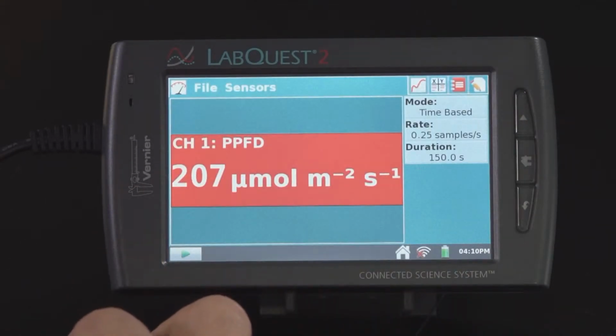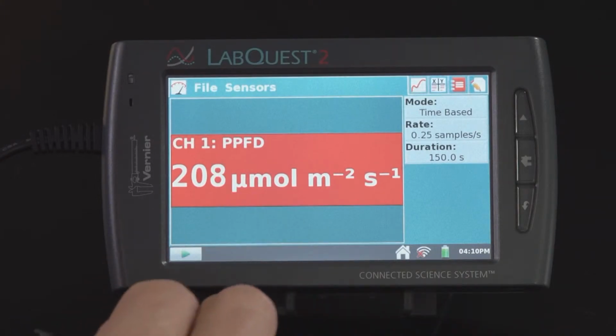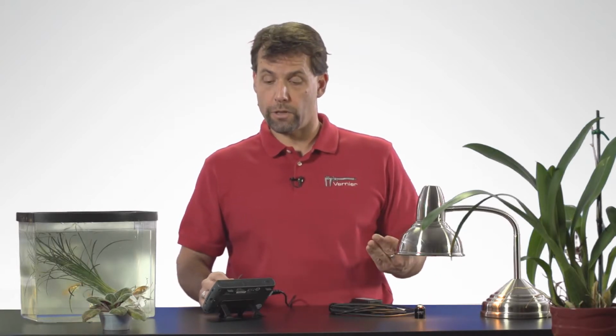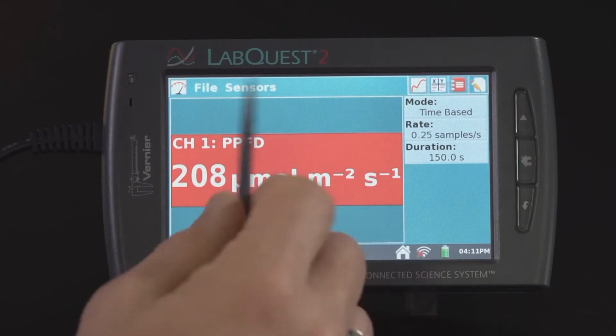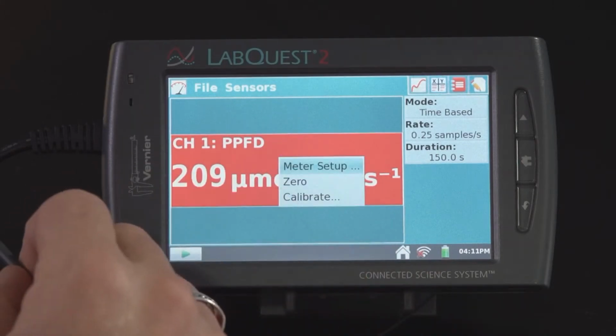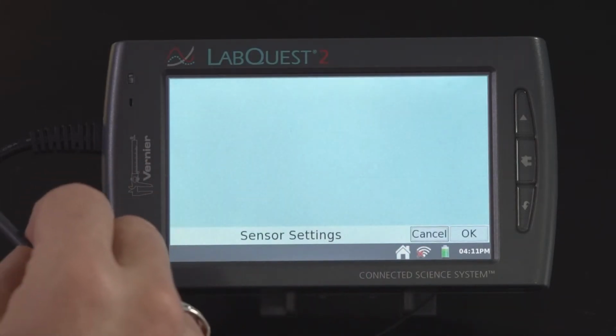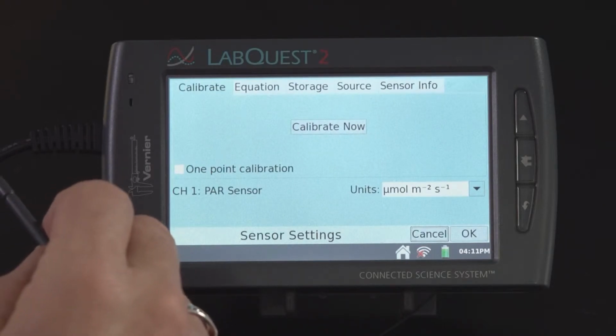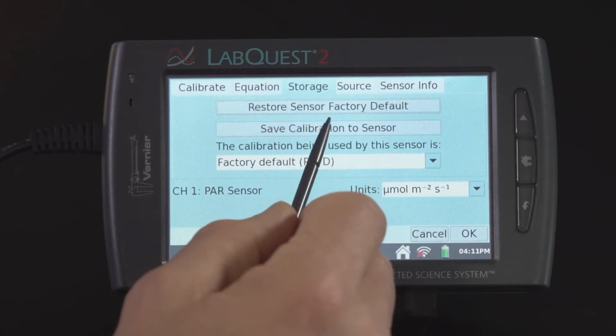And now we can see that the PAR sensor is reading a little bit lower at around 207, 208 PPFD. Now, if you want to store this calibration on the sensor so that every time you plug it in, it actually comes up pre-calibrated for use on artificial lights, that's quite simple as well. Just tap on the meter screen, go to Calibrate, and then select the Storage tab. And right now, all I need to do is say Save Calibration to Sensor, and then it would be stored.